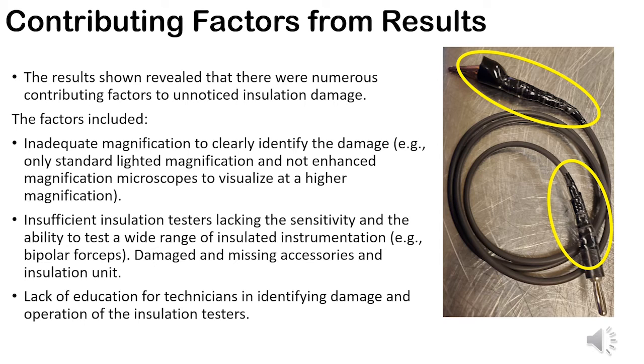Also, insufficient insulation testers lacking the sensitivity and the ability to test a wide range of insulated instrumentation. For example, bipolar forceps, damage and missing accessories were also noted in the department. So to give you a better idea, insulation testers out there can range in sensitivity, sort of like driving a car. A car can range from a Toyota all the way up to a Tesla. Insulation testers are similar to that, meaning you could have something that's pretty basic, that has a very low sensitivity, but then you can have something that you actually have to set the voltage to a specific range for the type of insulation that you're testing. And lastly, there was a lack of education for technicians in identifying damage and the operation of the tester itself.